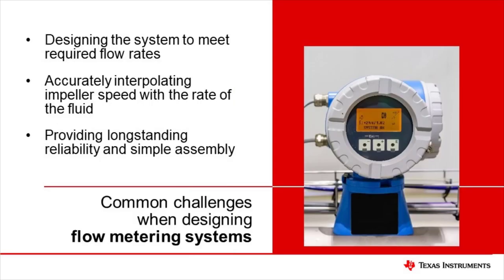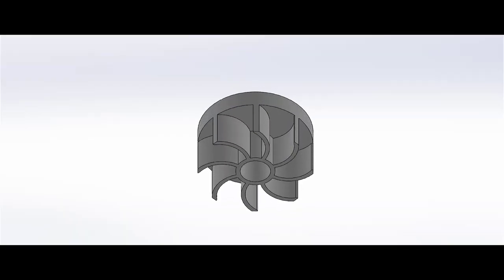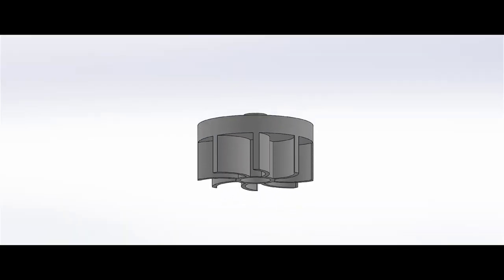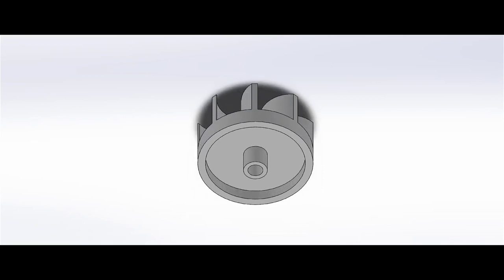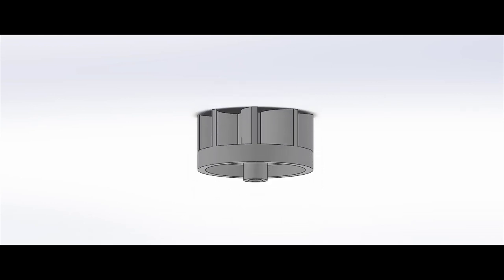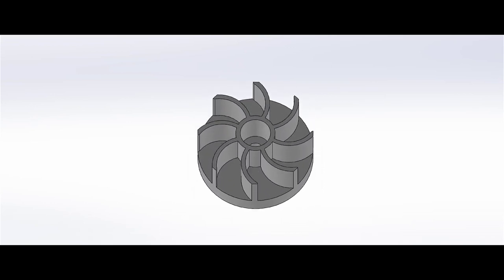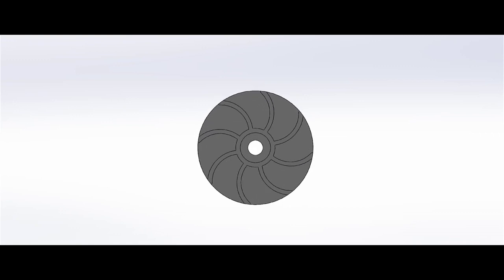In flow metering systems, it is important to be able to accurately determine the flow of a liquid. As the liquid flows through the flow meter, it rotates a mechanical assembly known as the impeller. The impeller is fixed with magnets such that a Hall sensor can detect the change in the magnetic field as the impeller rotates. The Hall Effect Sensor outputs a frequency which is proportional to the flow rate of a liquid.